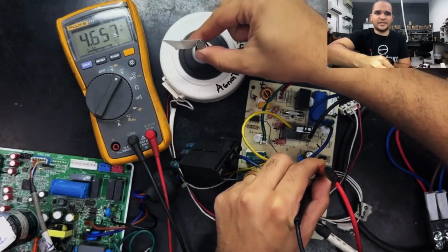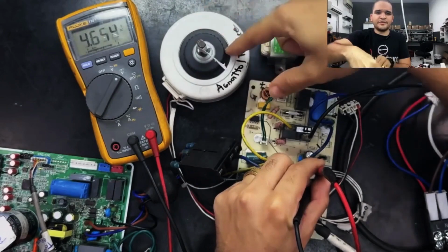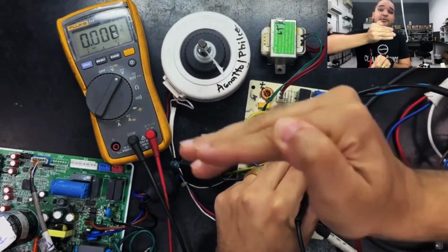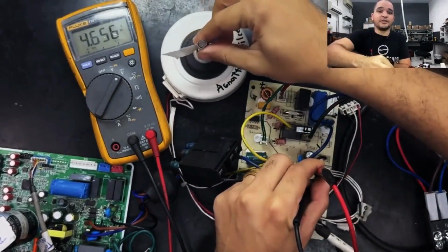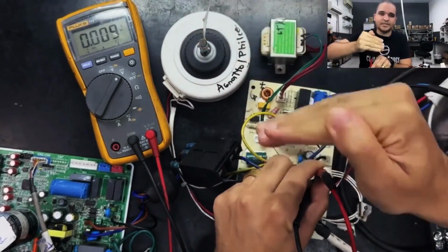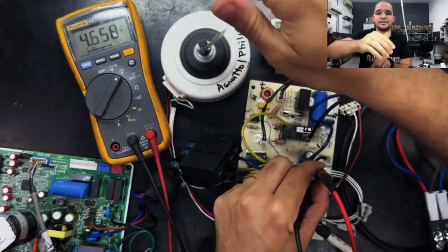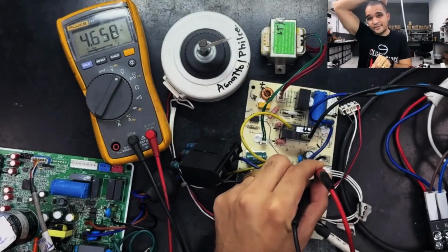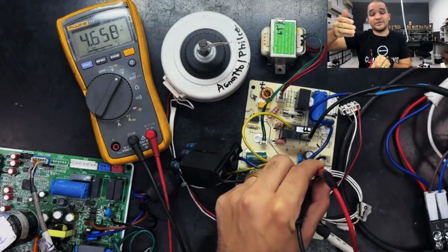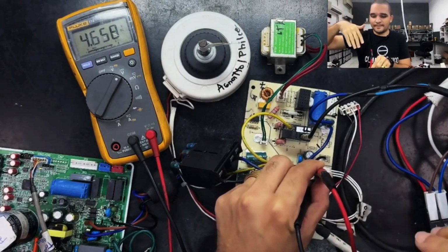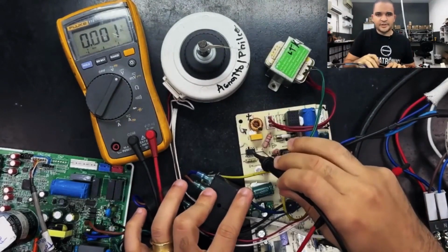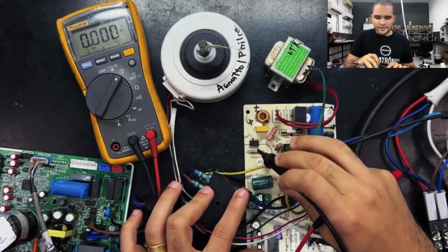If I rotate the motor, the signal fluctuates. It means the feedback is signaling. The feedback connector is exclusively connected. I am linking the ground pin to the output voltage pin, which functions as the signal pin, and I am manually rotating the motor to check if it oscillates between 0 and a higher voltage. It is indeed oscillating here between 0 and a higher voltage up to the maximum voltage of the power supply, which in this specific instance is 5 volts, correct? Consequently, it should oscillate between 0 and 5 volts. If the fan's power supply is 12 volts, it ought to oscillate between 0 and 12 volts.